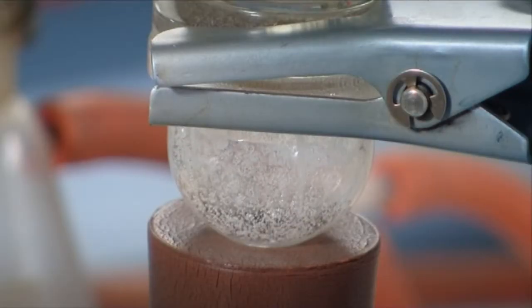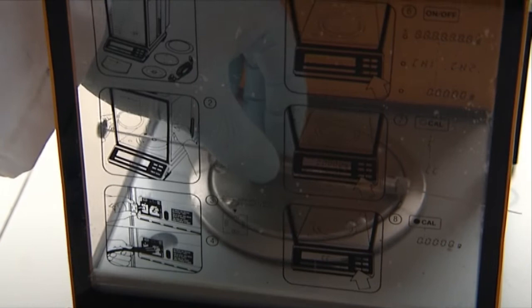So the oil is returned to the laboratories here at EA Technology and we complete moisture, acidity, electrical breakdown strength, and solid contamination tests. From this analysis, what we're trying to do is identify where the oil is on the oil degradation curve.